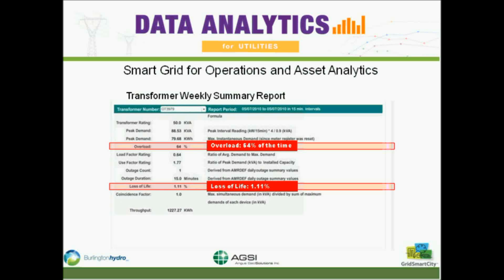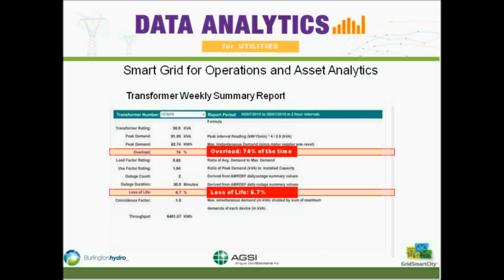We can also look at that for a week. It also happened to be the hottest week of the year, so it was overloaded for the entire week, 74% of the time, which is pretty high. It had 2 outage counts, and for the week, because it wasn't getting a chance to cool down, it lost 6.7% of its life.